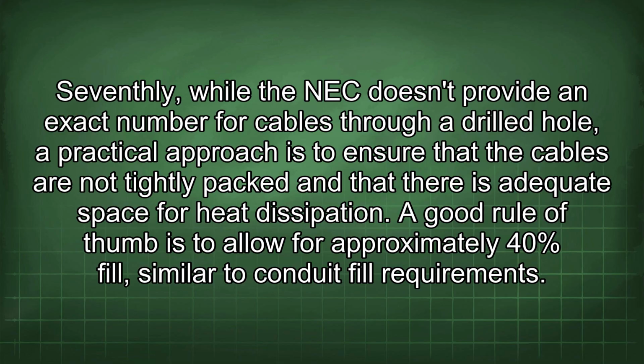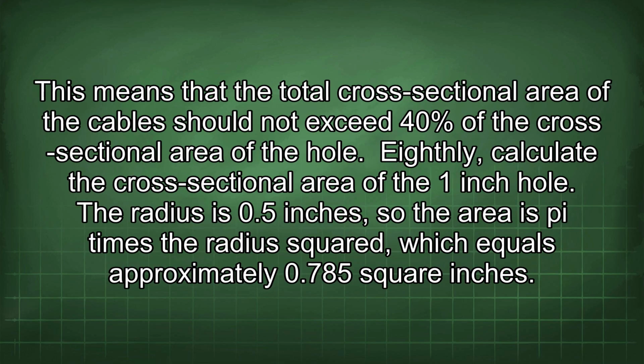Seventhly, while the NEC doesn't provide an exact number for cables through a drilled hole, a practical approach is to ensure that the cables are not tightly packed and that there is adequate space for heat dissipation. A good rule of thumb is to allow for approximately 40% fill, similar to conduit fill requirements. This means that the total cross-sectional area of the cable should not exceed 40% of the cross-sectional area of the hole. Eighthly, calculate the cross-sectional area of the 1-inch hole.